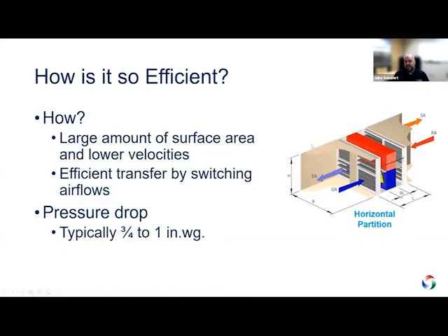So a number of questions come up when we talk about this technology. I guess the first one is, how is it possible that it can be so efficient? Well, there's a lot of surface area with this heat exchanger. Also, when you're talking about a rectangle, or square, you're using the entire face area of an air handler versus a wheel that's going to be a little bit smaller. And then just that process of switching the airflows and having a cold bank and a hot bank back and forth is a very efficient process.